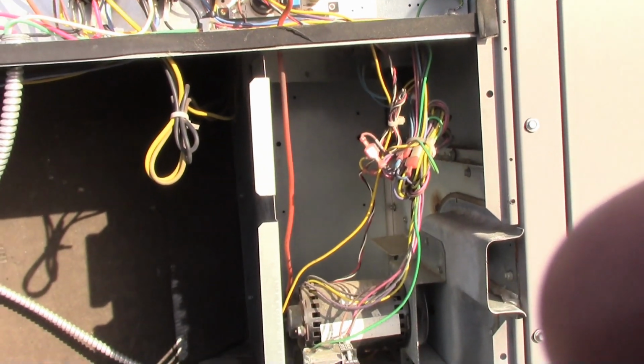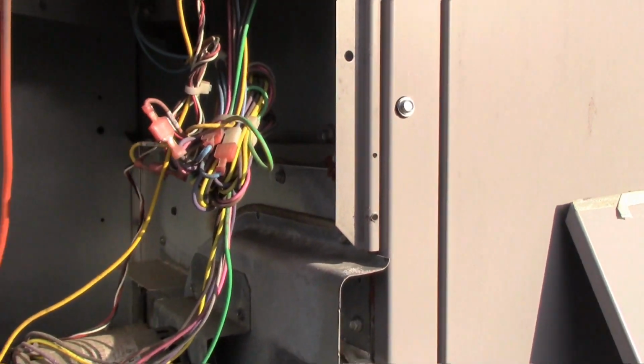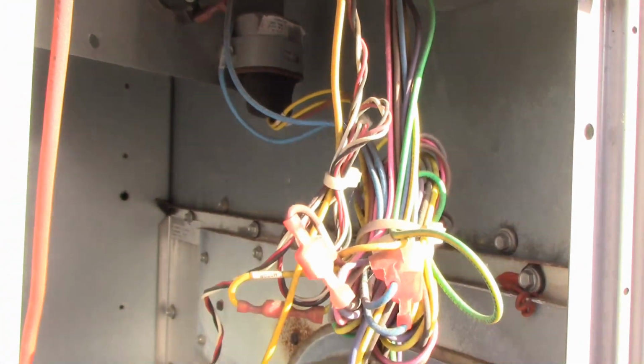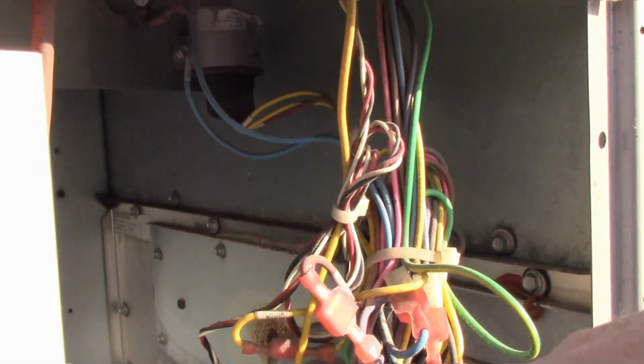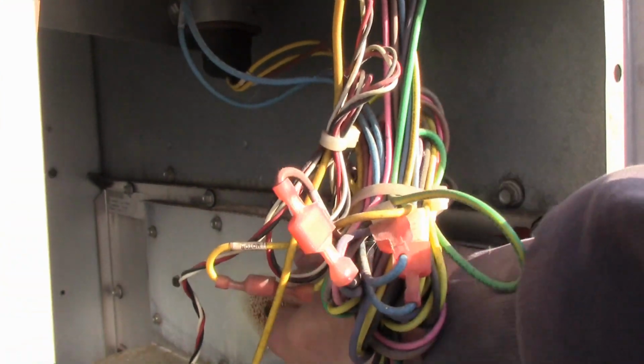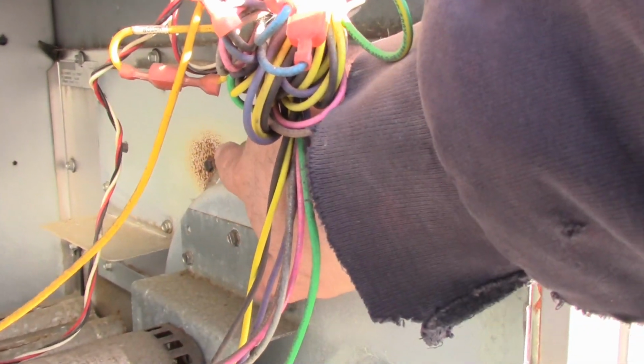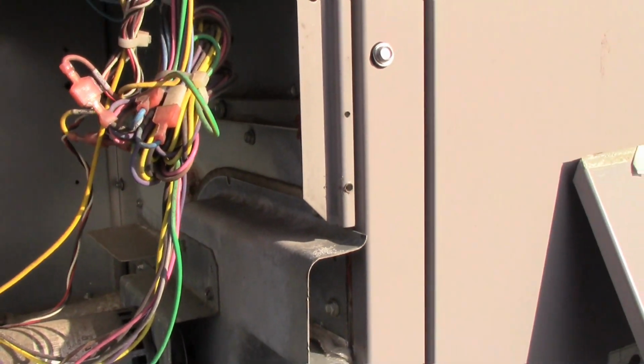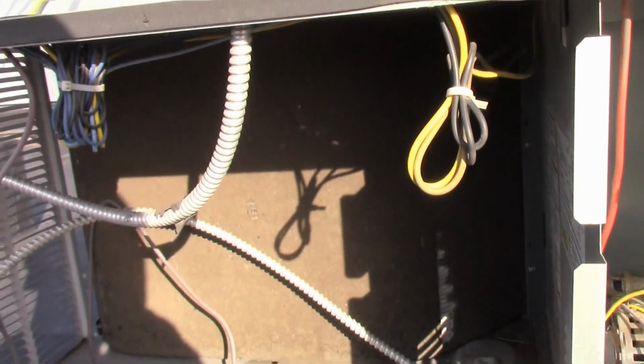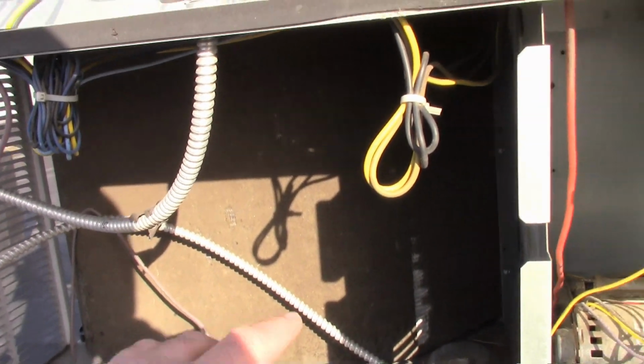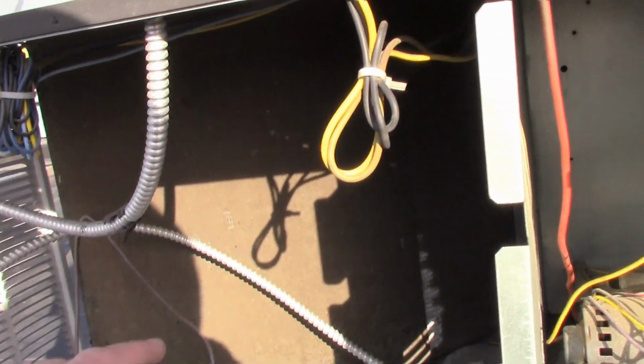Alright, so I got the panel off. Quick visual inspection of a normal Carrier trait is this wall here rotting out. And a little rust mark on that screw. You can see it back there. Right about there, but it's not all the way through. The wall doesn't look bad. That coil needs to be cleaned though. A lot of people with these little 5-ton Carriers, just be aware.